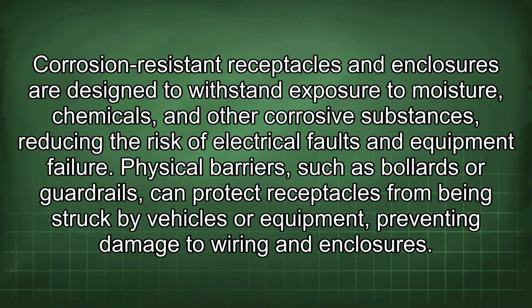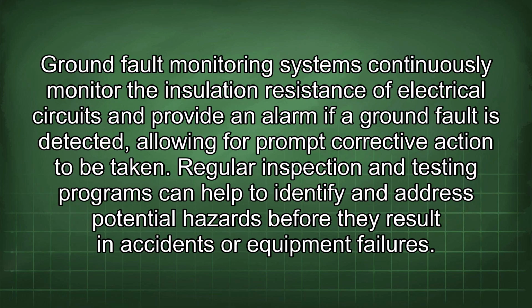Corrosion-resistant receptacles and enclosures are designed to withstand exposure to moisture, chemicals, and other corrosive substances, reducing the risk of electrical faults and equipment failure. Physical barriers, such as bollards or guardrails, can protect receptacles from being struck by vehicles or equipment, preventing damage to wiring and enclosures. Ground fault monitoring systems continuously monitor the insulation resistance of electrical circuits and provide an alarm if a ground fault is detected, allowing for prompt corrective action to be taken.